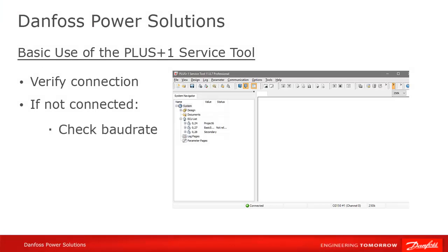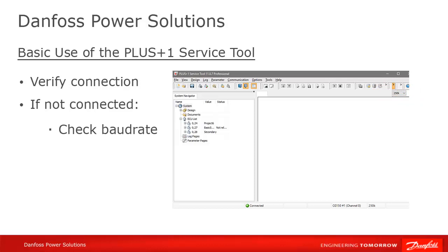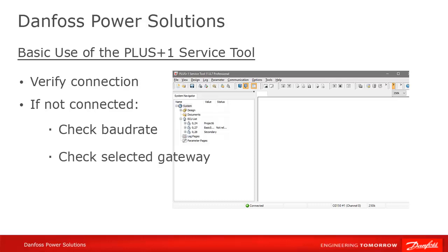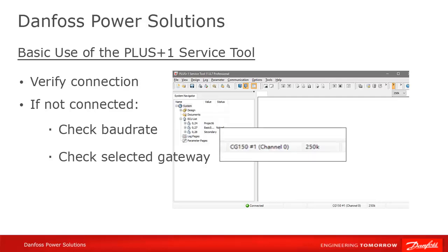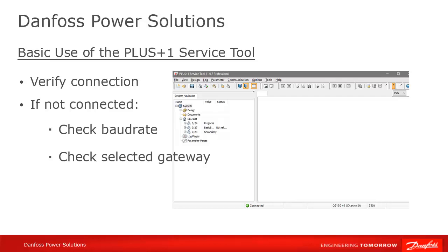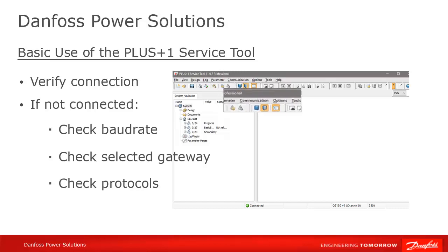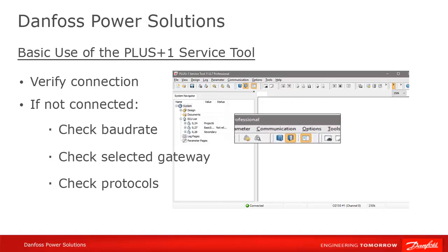Check your baud rate, verifying that all the other devices on the bus are using the same baud rate. Verify that you have a valid gateway selected. If using the CG150, make sure that you're not using a virtual gateway. And make sure that you have the correct protocols activated — at a minimum, make sure that the Plus One protocol is selected. These settings can all be found in the Communications menu.